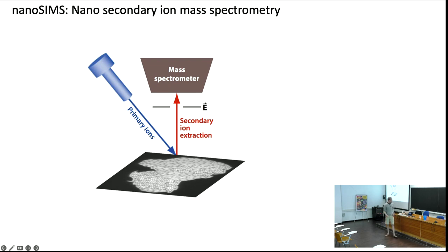I said on this image, the positive ions, they're kind of getting sucked into this negative plate, and then these negative ions are getting rejected. But the ion extraction efficiency of those negative ions is not equal for different species. And so we did a test, and I don't have the data in these slides, but it looks like, for example, the 13C ions start to get rejected a little bit sooner than the 14N carbon, the cyanide ion. I don't know why that is, but it's really, really interesting, and it's super important for these types of studies.